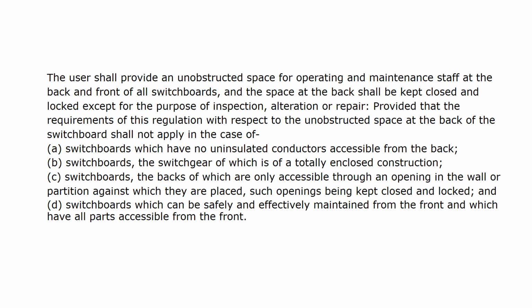Switchboards. The user shall provide an unobstructed space for operating and maintenance staff at the back and front of all switchboards, and the space at the back shall be kept closed and locked except for the purpose of inspection, alteration, or repair, provided that the requirements of this regulation with respect to the unobstructed space at the back of the switchboard shall not apply in the case of switchboards which have no uninsulated conductors accessible from the back, switchboards, the switchgear of which is of a totally enclosed construction, switchboards, the backs of which are only accessible through an opening in the wall or partition against which they are placed, such openings being kept closed and locked, and switchboards which can be safely and effectively maintained from the front and which have all parts accessible from the front.